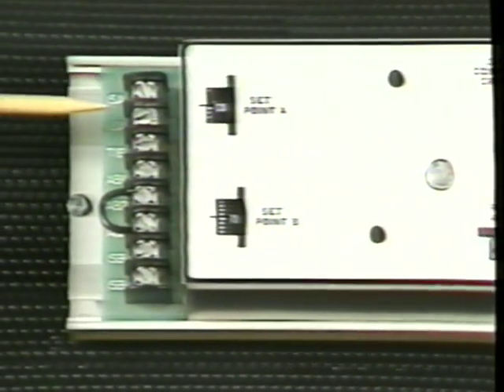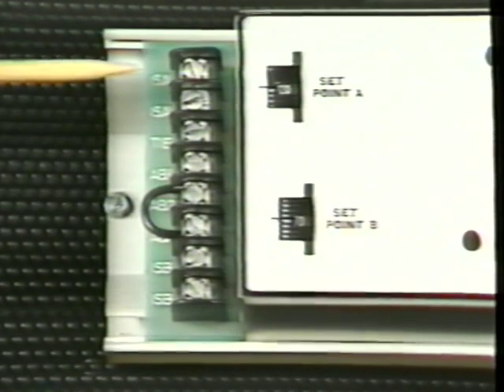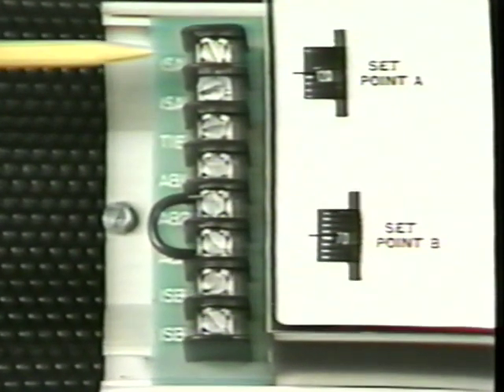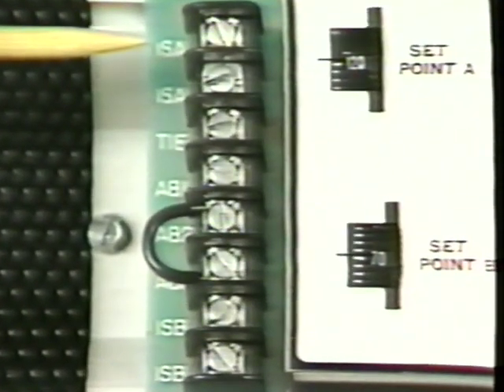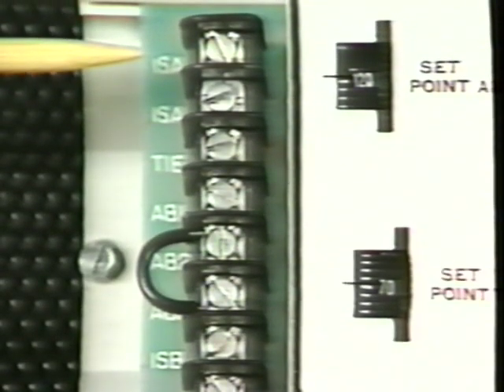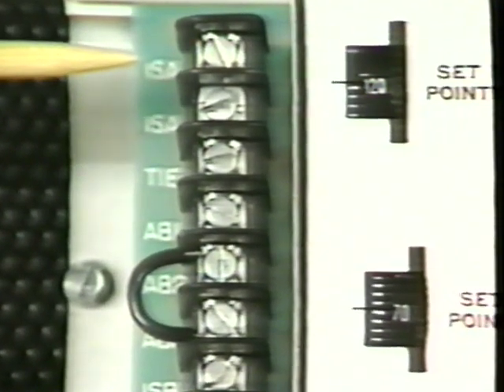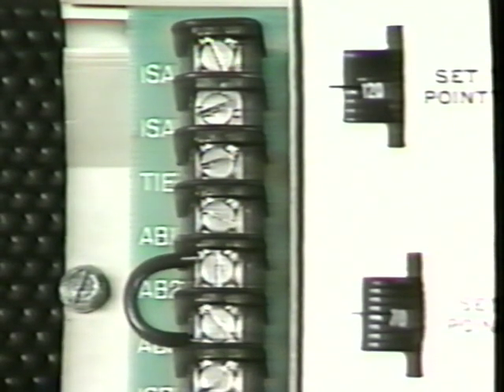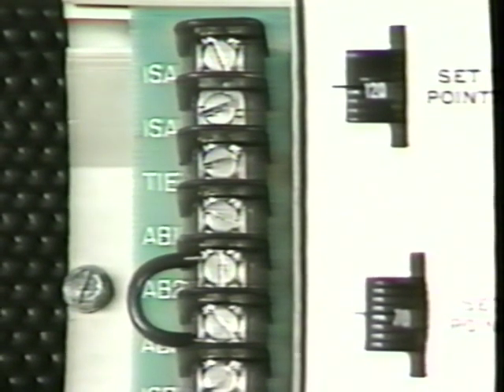ISA, ISA. 2 input terminals for sensor A, the control sensor. The sensor itself may be any 1000 ohm Balco element. For example, TS8201, the duct immersion sensor. Whatever the sensor, the variable being measured is the one being controlled.